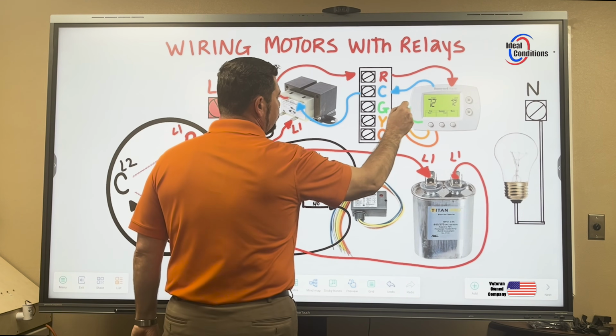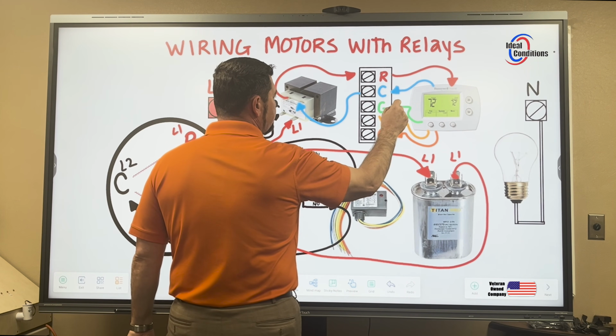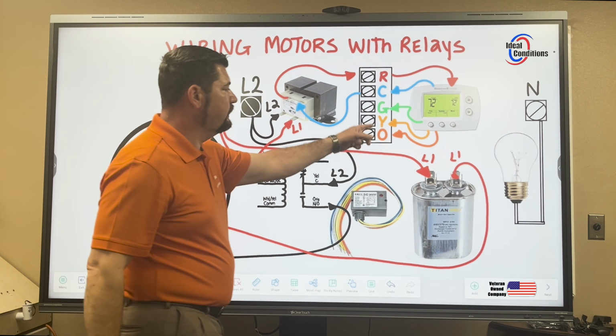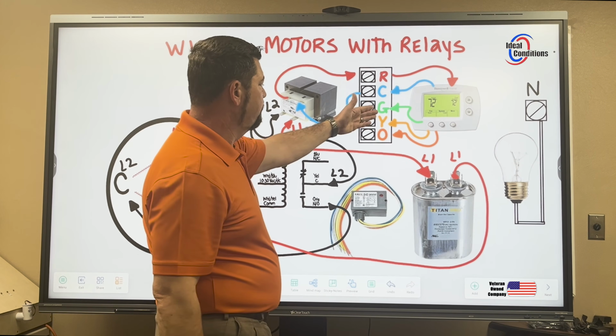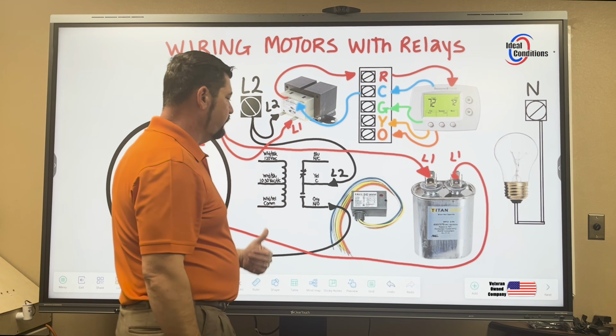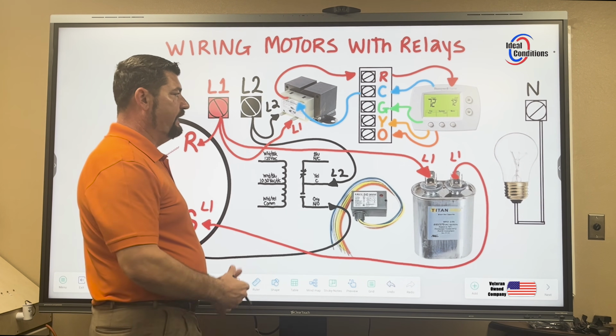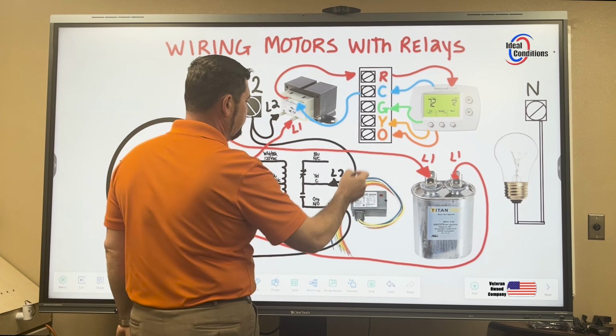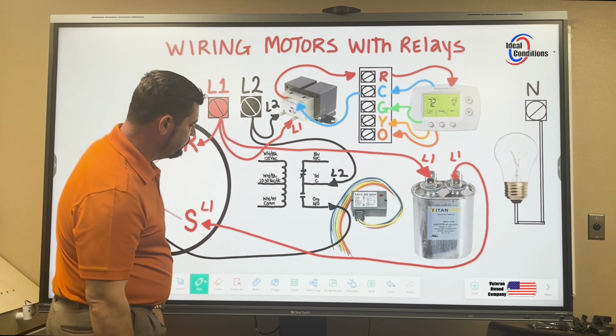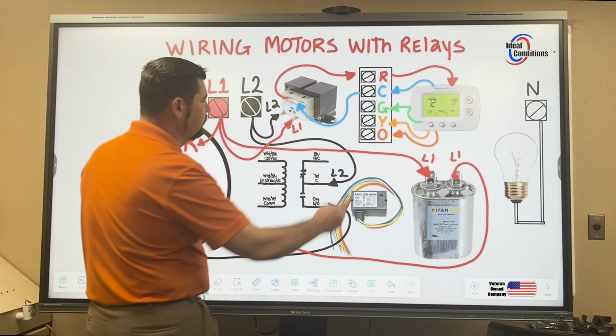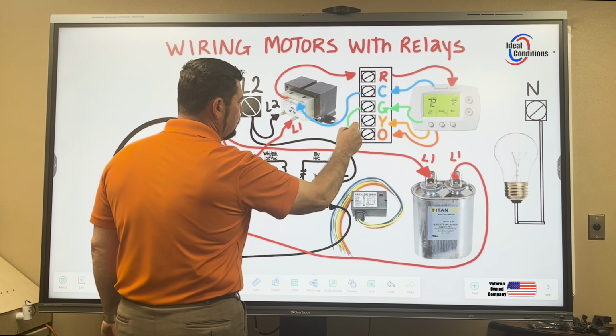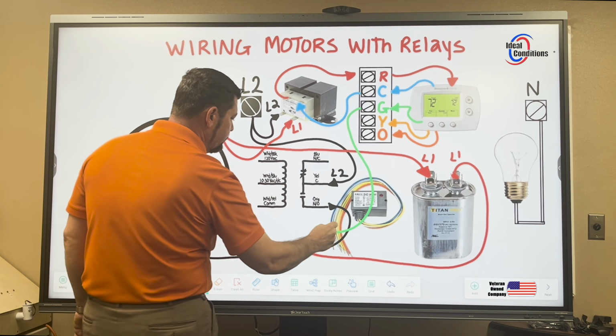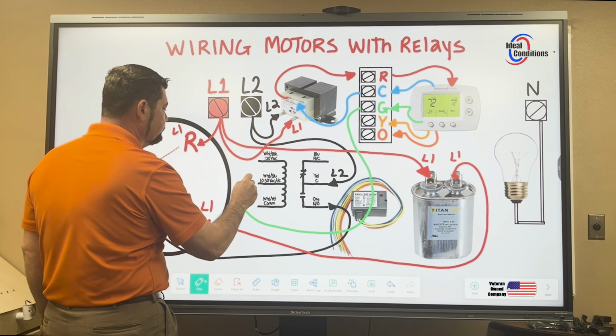G is energized by the thermostat to get the fan to come on for any one of these other modes. But mainly if the thermostat needs to call for the fan to come on by itself, just for fan on, it can now do that. How do I want to run this so it's clean? I'm going to come down just like inside your air handler.